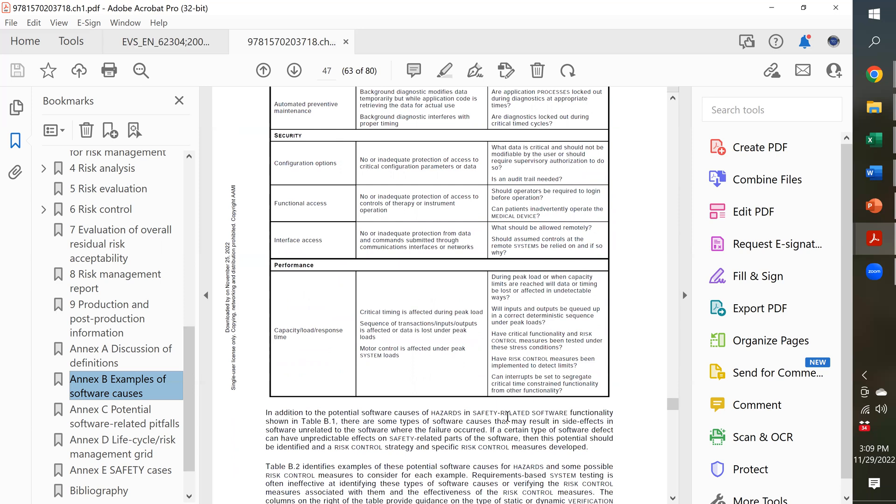Now, not all of them might apply. But before you say, we don't have any security concerns, the FDA has its own questions that it asks to make sure that there aren't any cybersecurity risks for your software. So, for example, if you have any Wi-Fi connection, any Ethernet connection, you have any USB ports where somebody can push something in and connect it, those are all things that are going to cause potential security concerns for your software.